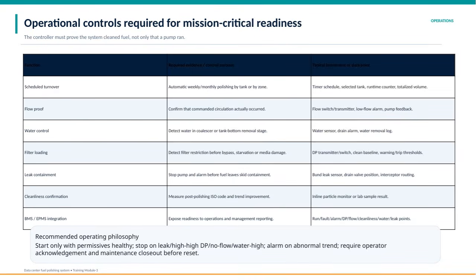Let's dive into the operational controls necessary for ensuring mission-critical readiness of the fuel polishing system. It's not enough for the controller to just show that a pump ran. It must prove that the system actually cleaned the fuel. This distinction is crucial for maintaining fuel quality and system reliability. Looking at the operations table, we have several key functions, each with specific evidence or control purposes and typical instruments or data points used. For scheduled turnover, automatic polishing happens weekly or monthly, controlled by timers and monitored through runtime counters and totalized volume to ensure adequate treatment.